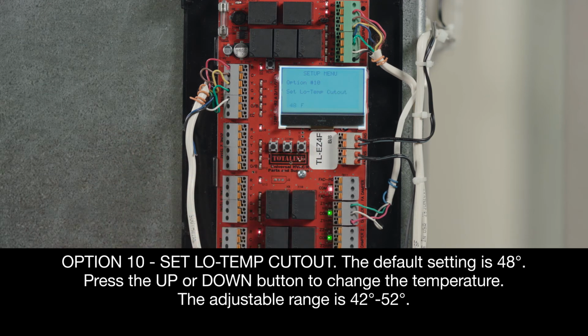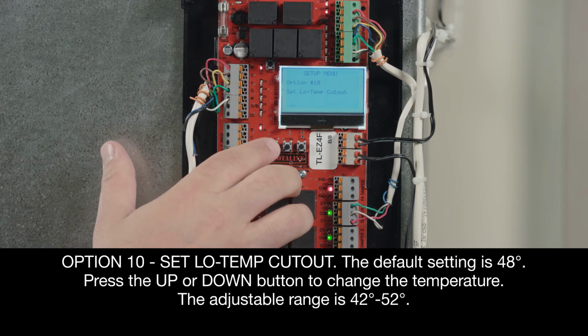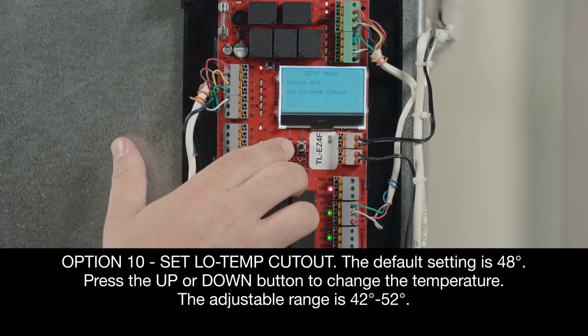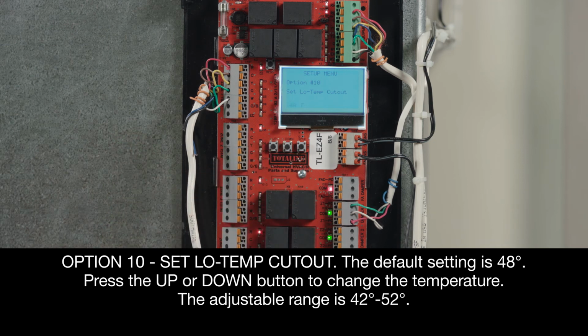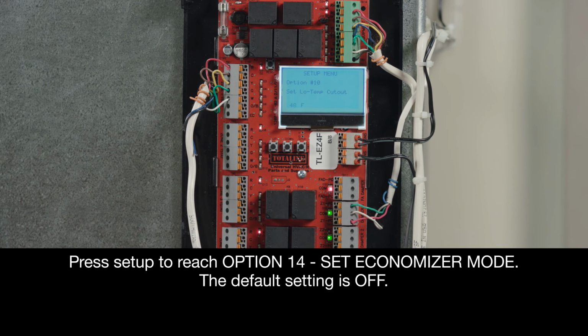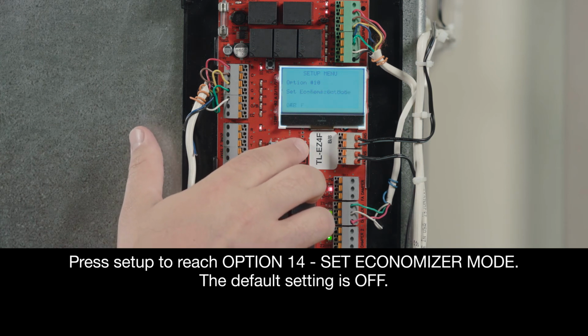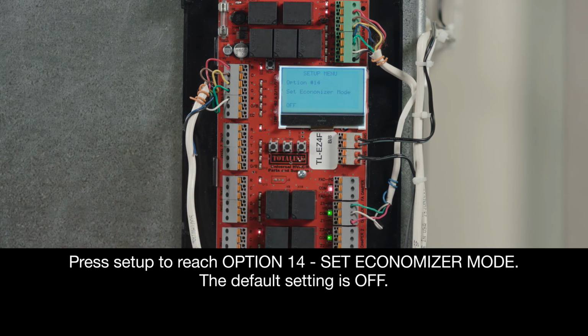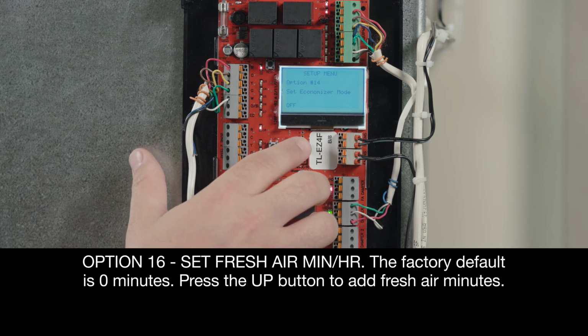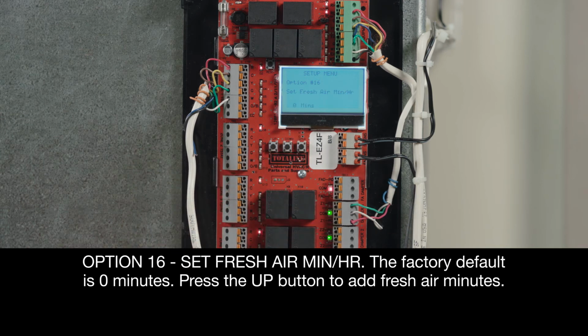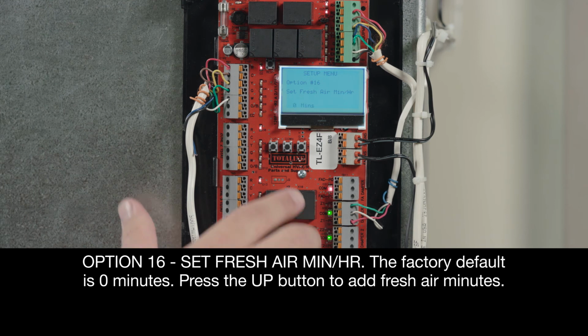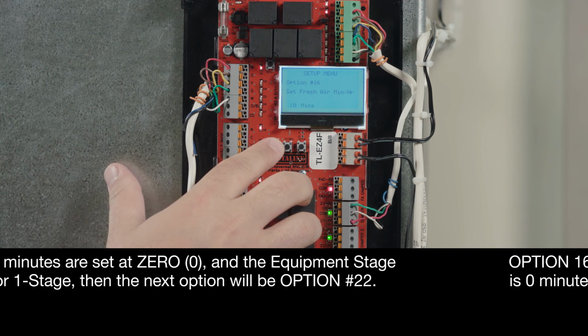Next, option 10, Set Low Temp Cutout. The default setting is 48 degrees. Press the up or down button to change the temperature. The adjustable range is 42 to 52 degrees. Now we'll press Setup to reach option 14, Set Economizer Mode. The default setting is off. And let's go to option 16, Set Fresh Air Minutes Hours. The factory default is 0 minutes. Press the up button to add fresh air minutes.